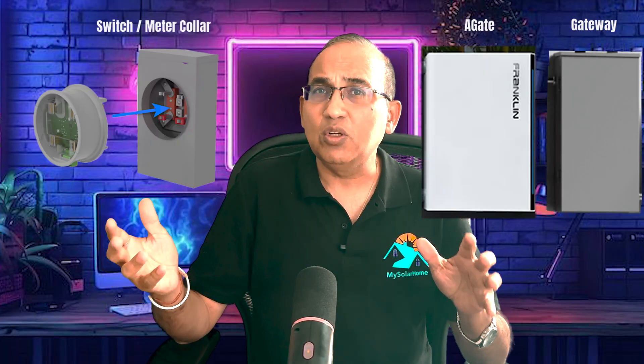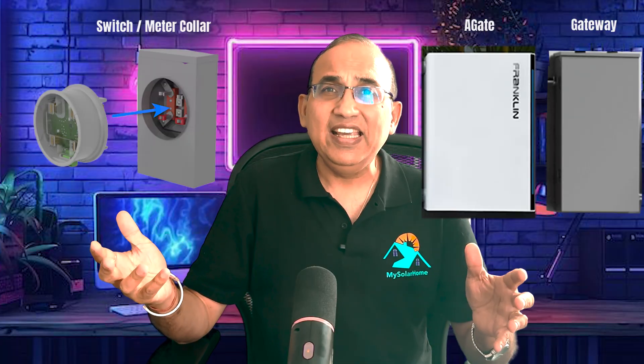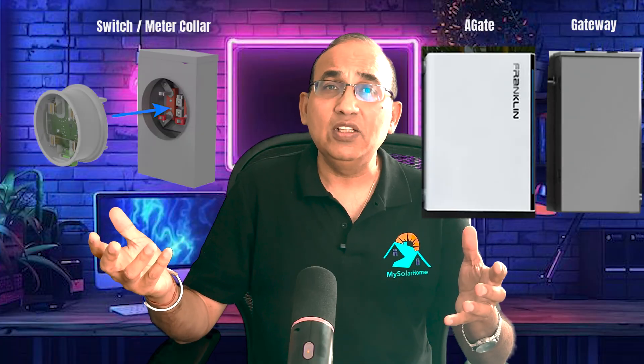The hero really is the gateway. The gateway is sometimes called a switch, AGate, backup switch, or Gateway 3. It monitors the grid and detects outages, and within milliseconds it isolates your home and lets your solar panels and battery continue to safely power your home and its circuits.